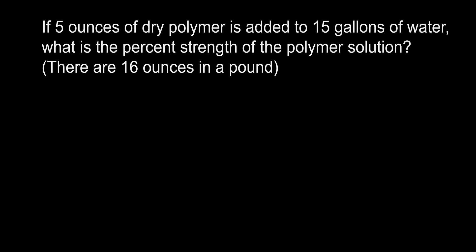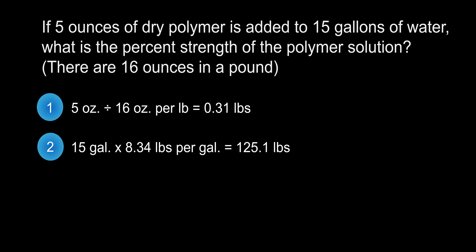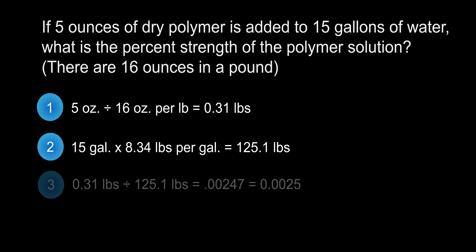All we need to do is figure out some simple unit conversions and turn it into a percent. It doesn't matter if you round your answers — your final answer will be very close to the correct choice if you follow these steps. First, convert ounces of dry polymer into pounds: divide 5 ounces by 16 ounces per pound, which equals 0.31 pounds. In step 2, convert gallons of water to pounds. One gallon of water weighs 8.34 pounds, so multiply 15 gallons by 8.34 pounds per gallon, giving 125.1 pounds. Next, divide pounds of dry polymer by pounds of water: 0.31 divided by 125.1 equals 0.00247, which rounds to 0.0025.